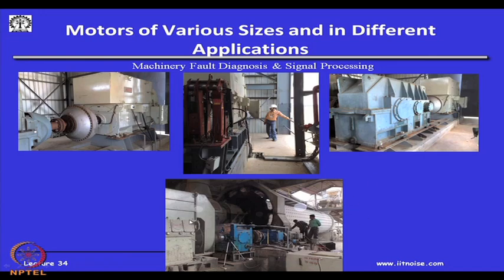And this is the view of another motor which has a massive reduction gearbox. This is actually the rotary kiln of that cement plant I was talking about, and you can see the dimension compared to this person. This motor rotates at 1440 rpm, but this kiln is only rotating at 2 to 3 rpm. So, there is a heavy reduction gearbox here as well. Critical to a plant are these gearboxes and these motors. If the motors die, your plant does not operate.